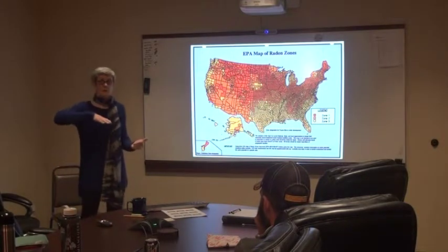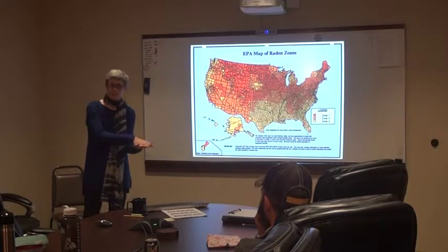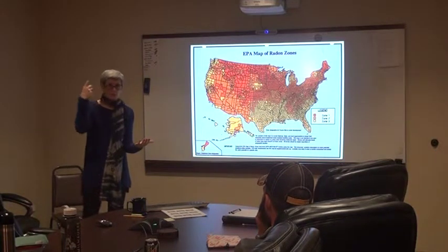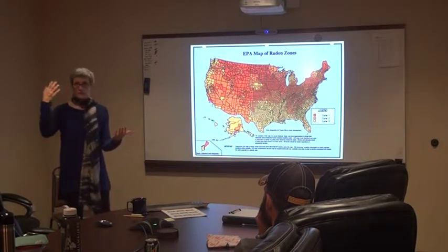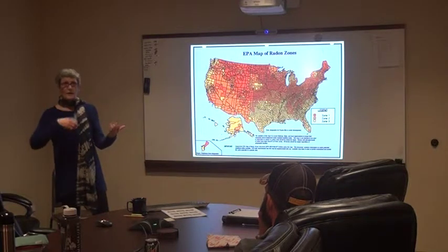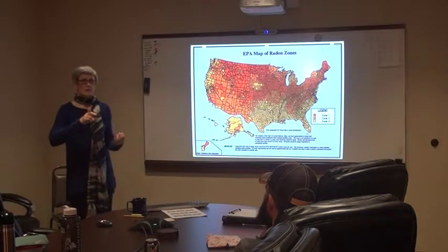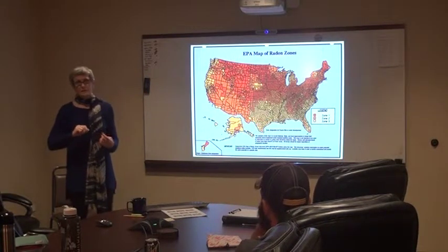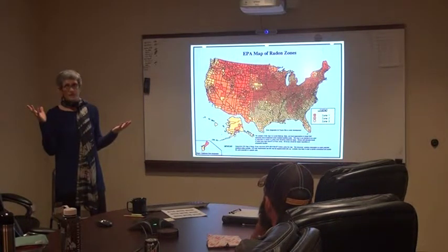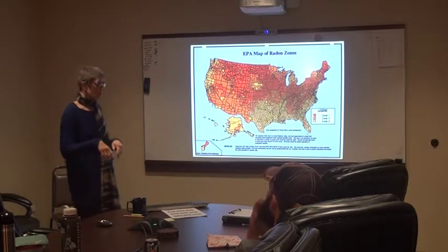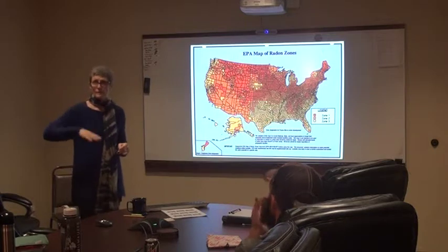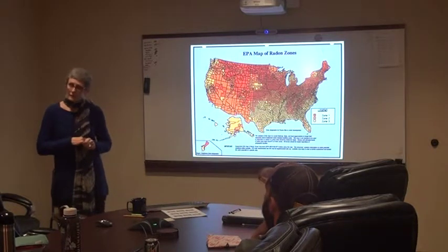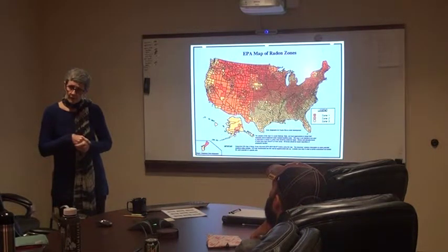And I've had radon levels where, they typically say the basement's going to be the highest level, but because we pick up that air from the basement, from the furnaces, and move it all around the house, I had one house in the study where upstairs was the highest level. It was just a little old house. It was pretty leaky, but it had a second floor and a basement, so you need to check on each level. Do you know the radon regulations for the existing homes?